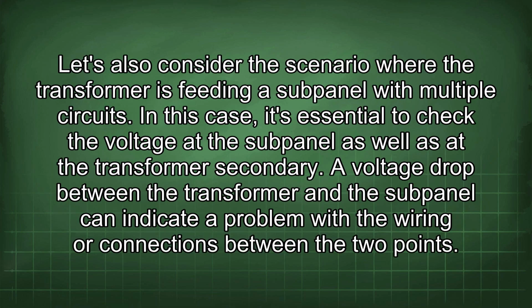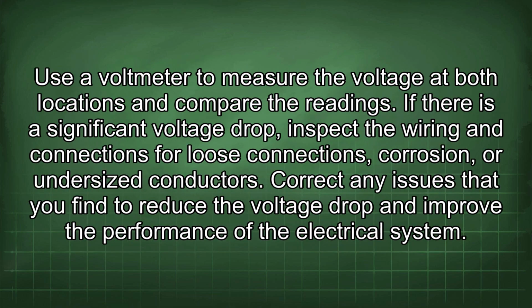Let's also consider the scenario where the transformer is feeding a subpanel with multiple circuits. In this case, it's essential to check the voltage at the subpanel as well as at the transformer secondary. A voltage drop between the transformer and the subpanel can indicate a problem with the wiring or connections between the 2 points. Use a voltmeter to measure the voltage at both locations and compare the readings. If there is a significant voltage drop, inspect the wiring and connections for loose connections, corrosion, or undersized conductors. Correct any issues that you find to reduce the voltage drop and improve the performance of the electrical system.